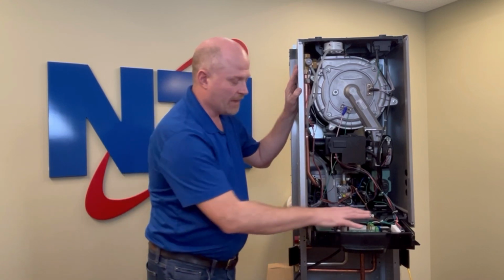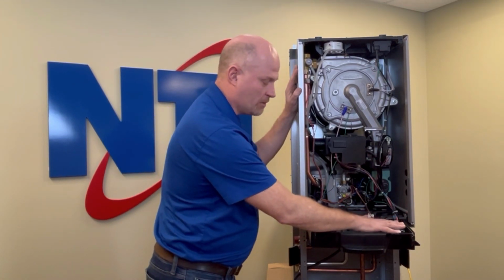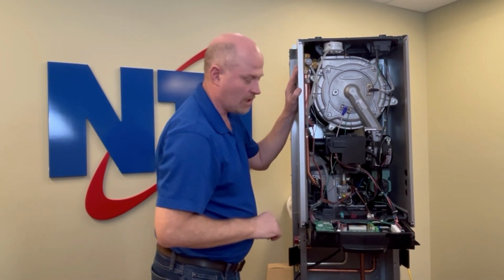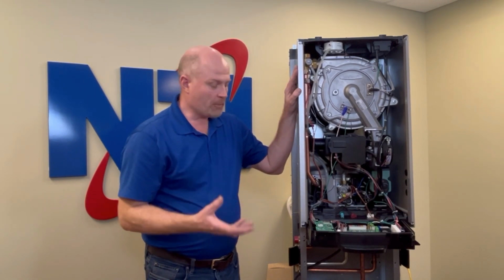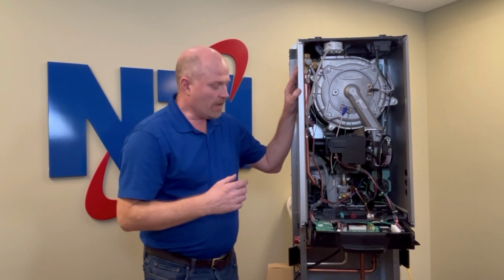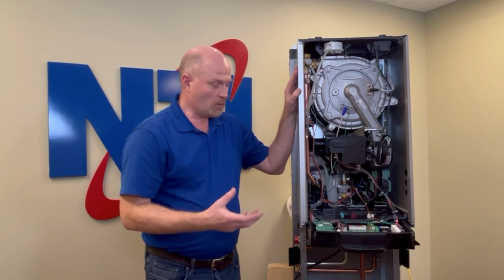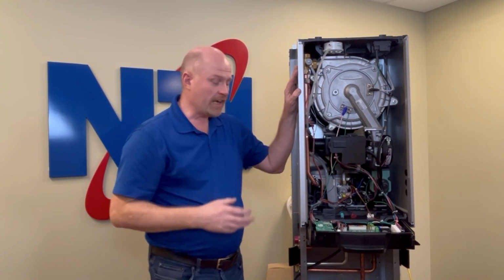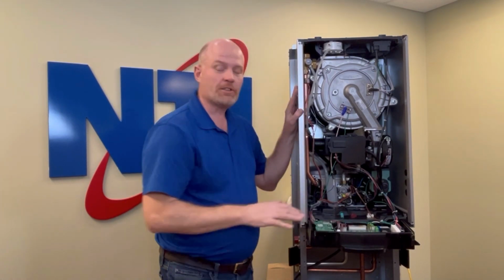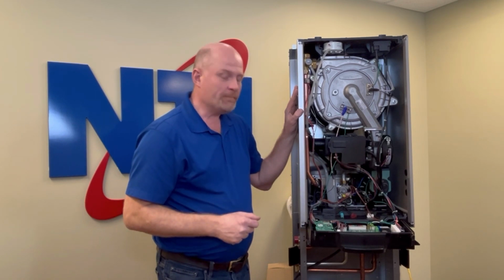If you have ongoing problems with internal faults and there's nothing found wrong inside the boiler or with the electrical connections coming to the boiler, it sometimes indicates that you have a power problem coming in from the outside world. If you're on an off-grid electrical supply, it's a good idea to check with your electrical contractor and see that the boiler is properly grounded and that the system is working properly.